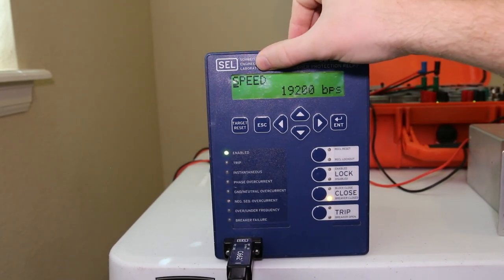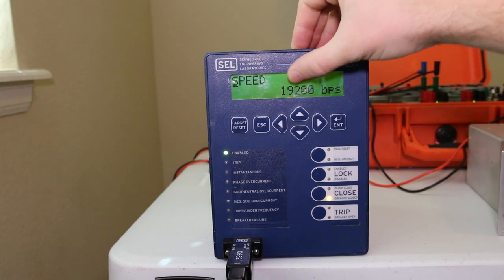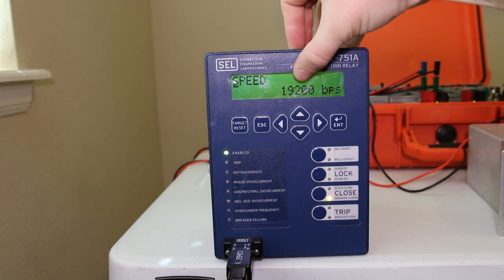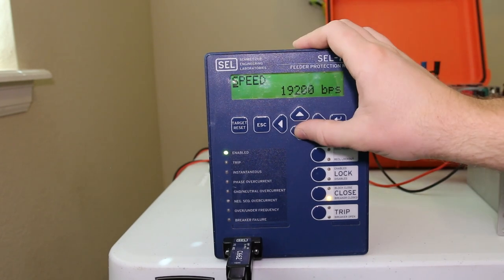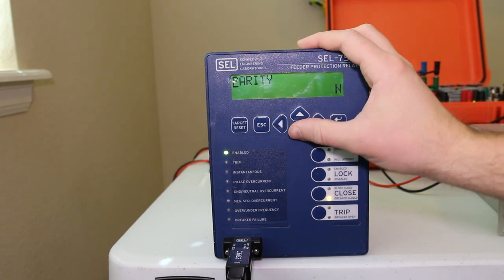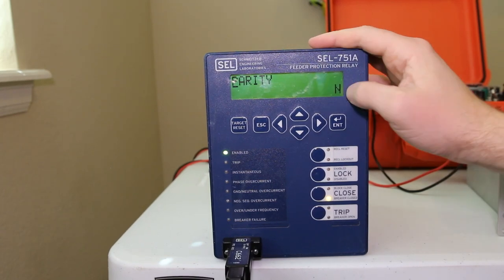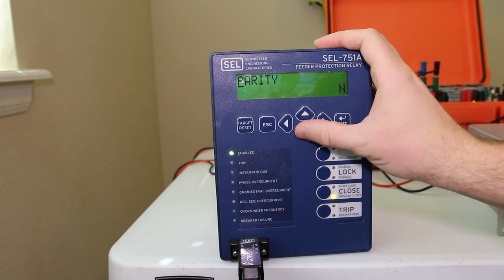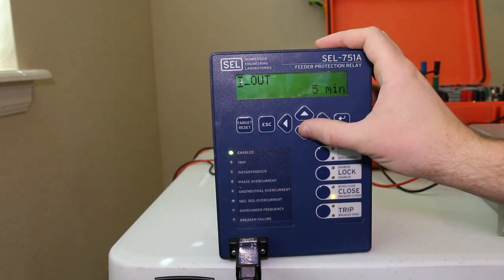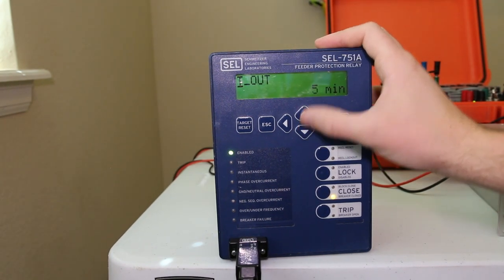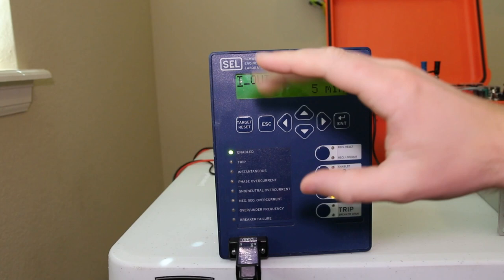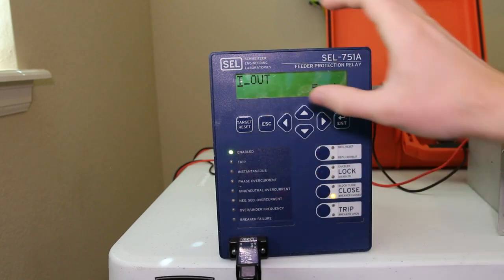So the speed on this one, the communication speed, the baud rate is 19,200. So 19.2, that's good. Scroll down. 8 communication bits. The parity on this one is N for none. And then 1 stop bit. Again, this is RS232. So the communications protocol is very old school, very granular. It doesn't do any auto detect stuff that USB does.